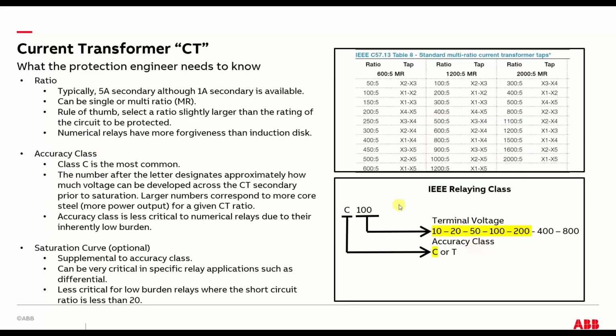Let's see. So your accuracy class, going back to that point of how much it can drive, say you had a C, and most of them are usually classified as C. The terminal voltage part of it, so if it's a C100, it can drive 100 volts of load without saturating. Normally a CT is shorted, obviously, but whatever load it's driving through its short, whatever voltage develops there, that would be this number. This is not an exact correct explanation of what I'm saying, but it's sort of indicative. So basically, the higher the number, the higher the C class, the more load in terms of protective relays that CT can drive.